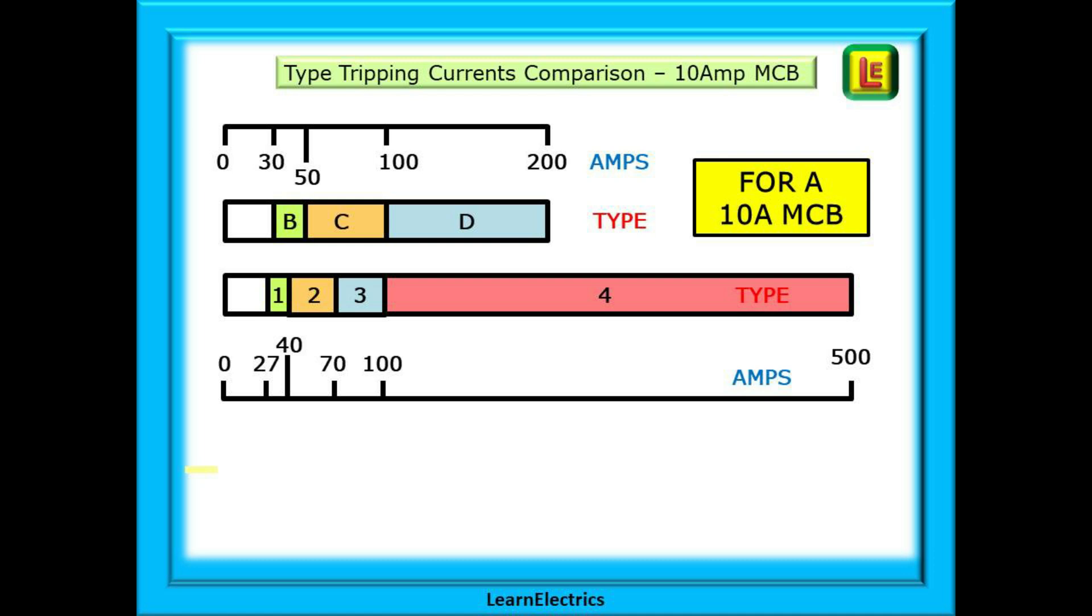Looking at the B, C, D row, the white area is the area of not tripping. So between 0 amps and 30 amps a B type will not trip. Between 30 amps and 50 amps a B type 10 amp breaker is in the ready to trip zone and at 50 amps, that is to say at 5 times 10 amps, it will definitely have tripped.